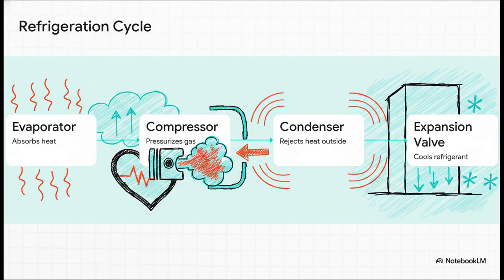It acts kind of like a sponge, soaking up the blazing heat from the servers and turning into a gas. Step 2 is the compressor, basically the system's heart, powerfully squeezing that gas until it's super pressurized and actually hotter than the outside air. Step 4, way at the end, cools things back down. But look right there at step 3, the condenser—this is our focal point for today. This is the ultimate exit door, where all that collected heat finally gets thrown out of the building.